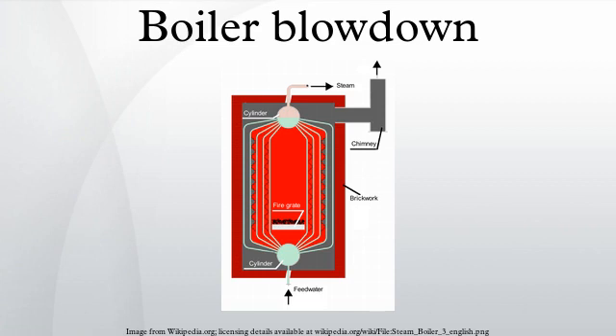Modern boilers discharge bottom blowdown to a blow-off tank where the blowdown can flash and vent steam upwards without entraining water which might cause burns. A pipe near the bottom of the blow-off tank maintains a water level below the blowdown entry point and allows cooler water remaining from earlier blowdown events to drain from the tank first.